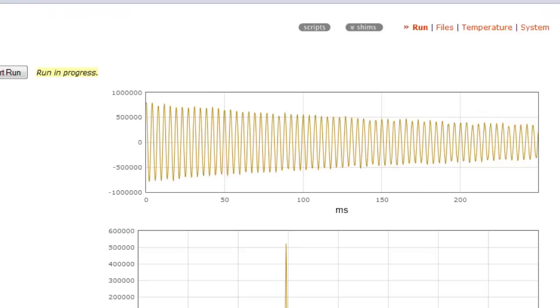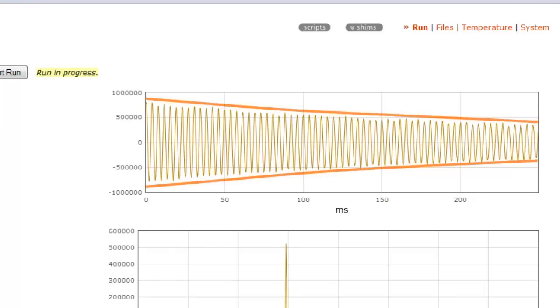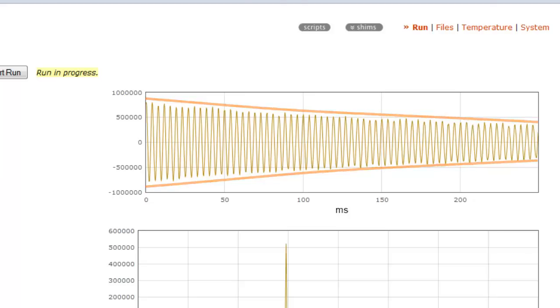The FID looks quite good. It has the appearance of a slowly damped sine wave. The FID displays here only the real or absorptive component of the complex data in the time domain. When we shim, we're trying to make homogeneous the magnetic field volume around the RF coil, within which is our sample. As we improve the magnetic field homogeneity, our signal becomes stronger, and the signal decay rate slows.